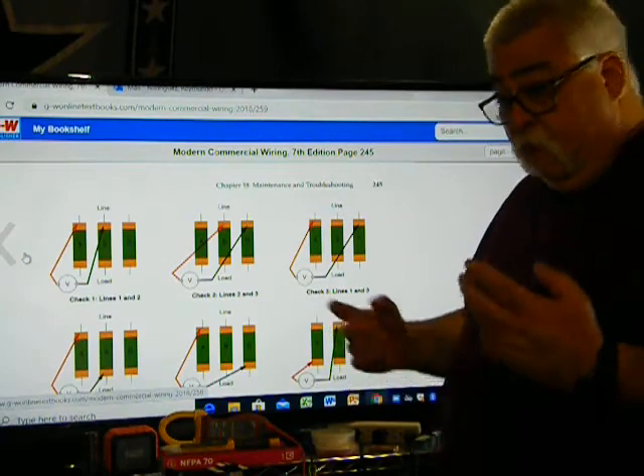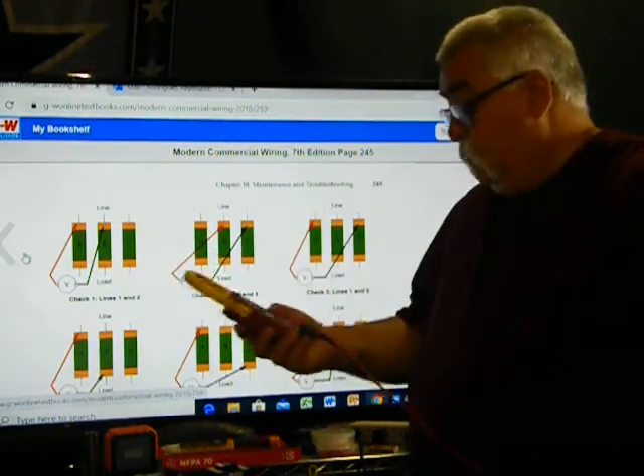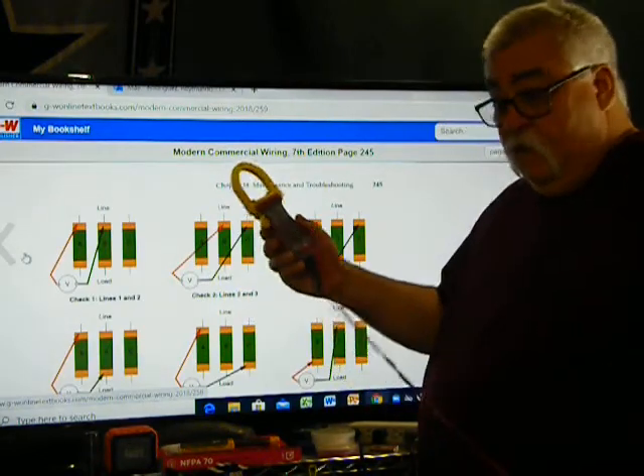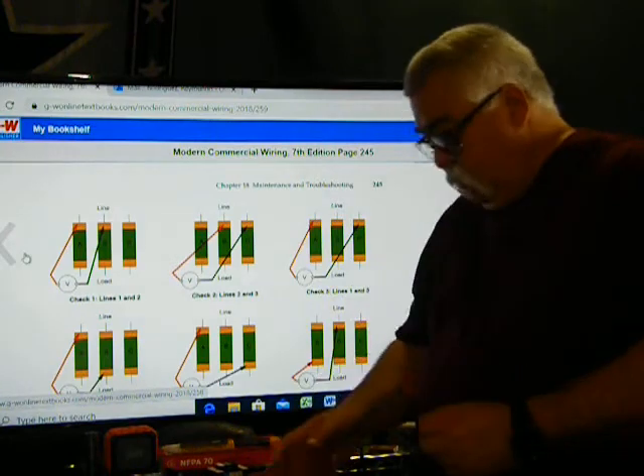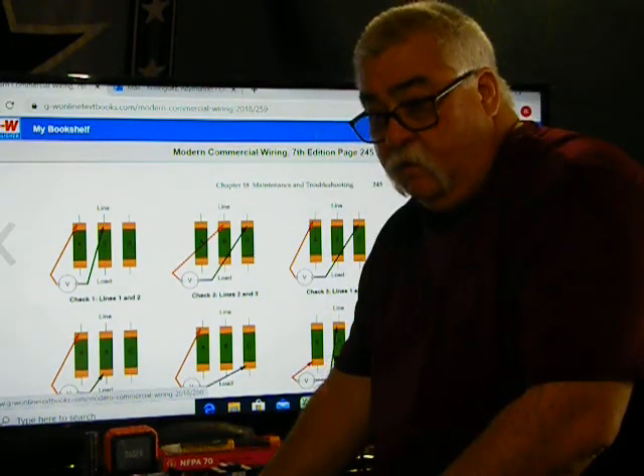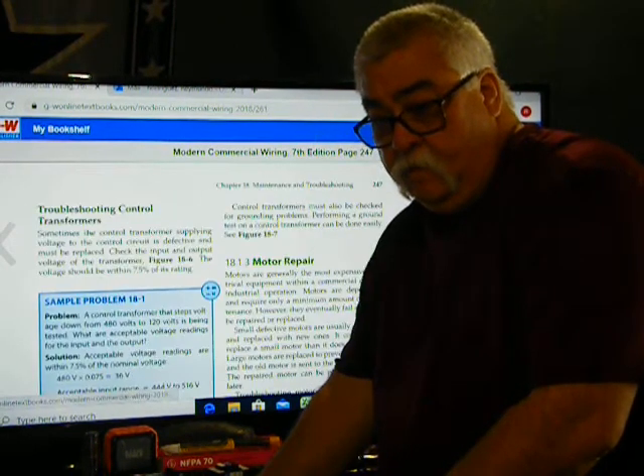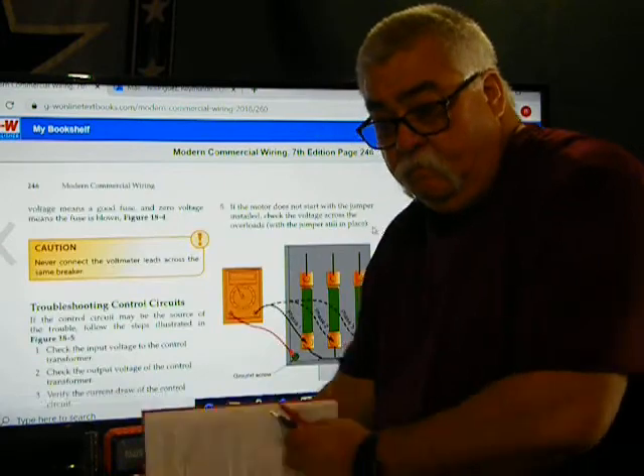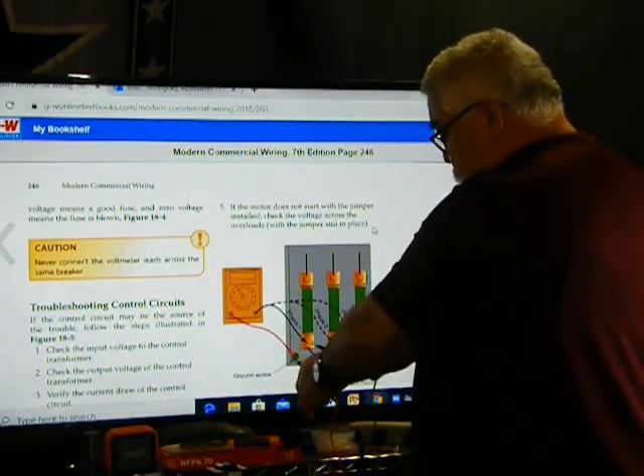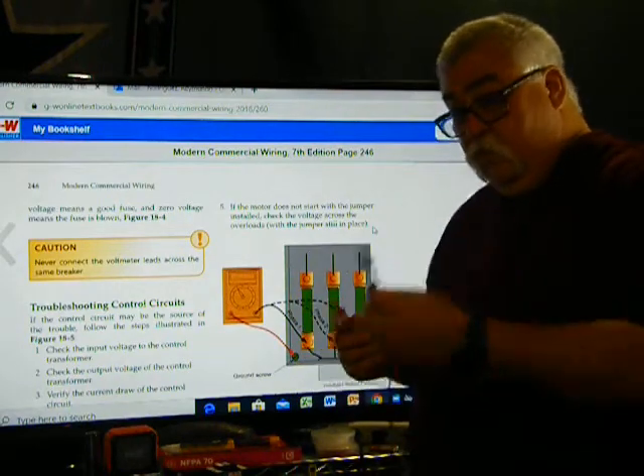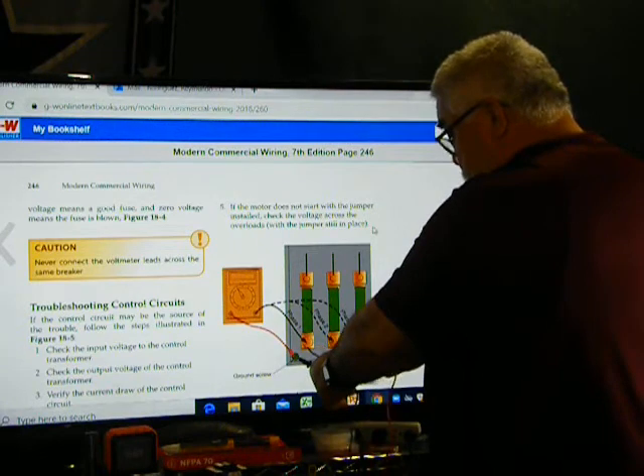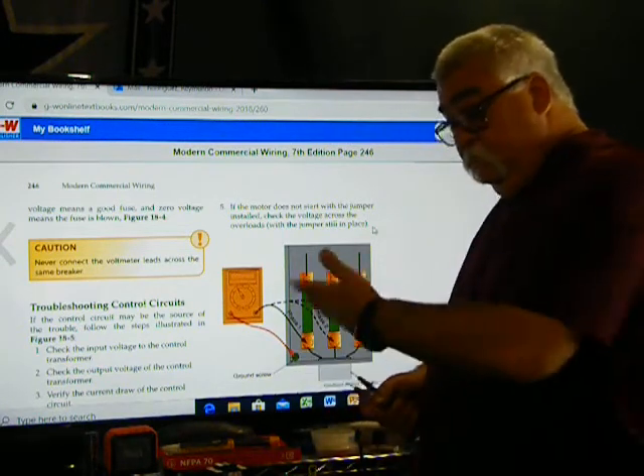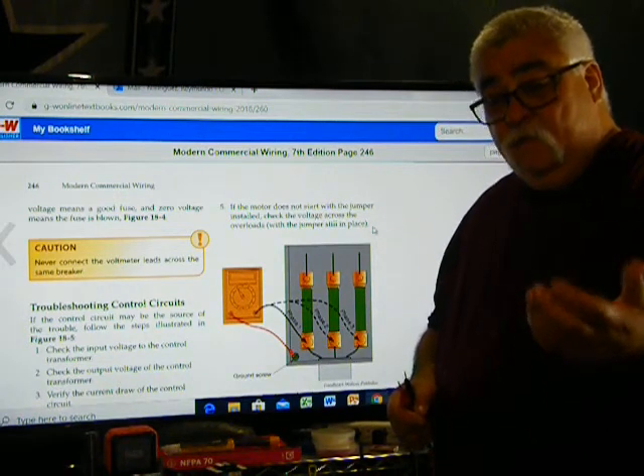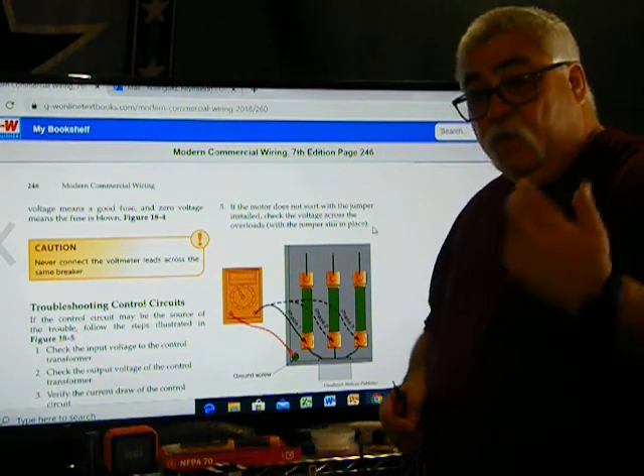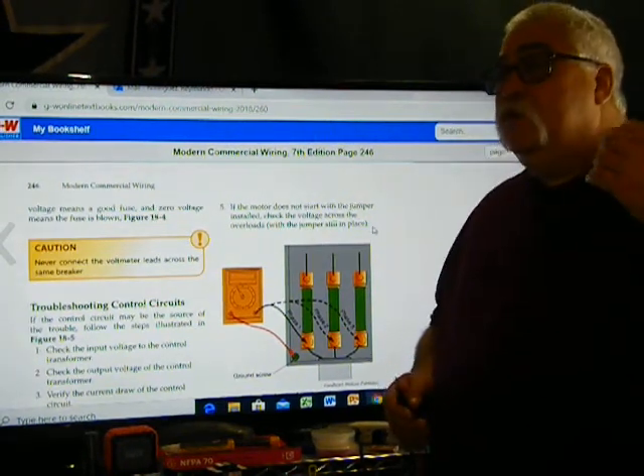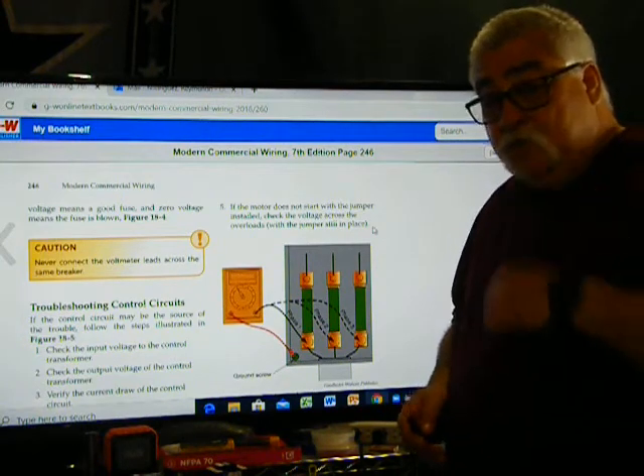And you get your amp probe, or you get your tester, your resistance tester. Say this one. I go to ohms. With ohms, what I usually do is, let me go to the next one. I like the other picture better. Doing a resistance test. Ground to here, to here, to here. Okay, so what I'm going to do is I'm going to go to ground and go to the fuse. Okay, yesterday one of the questions was, when you're doing resistance measurements, what don't you always do? You should never do resistance measurements on an energized circuit. So always make sure it's off.